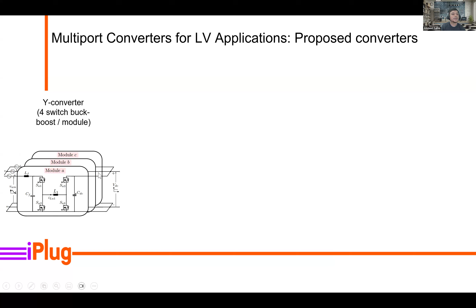We extended this topology first to what we call the multiport Y converter. Instead of having a 4-switch buck boost for each module, we extended to a 6-switch buck boost, so we interface the 3-phase AC grid with 2 DC ports. We still have single-stage power conversion, without any bulky components like intermediate DC link capacitors or high frequency transformers. We have bidirectional power flow and buck boost capability at all ports without any dependence on voltage, giving enhanced flexibility.